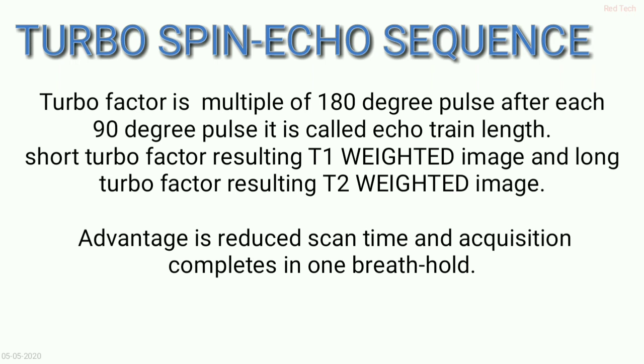You must remember: when you shorten the turbo factor, you obtain a T1-weighted image. When you increase the turbo factor — that is, increase the number of 180-degree pulses — you obtain a T2-weighted image.